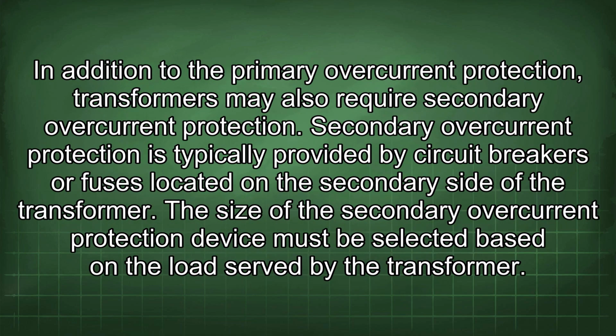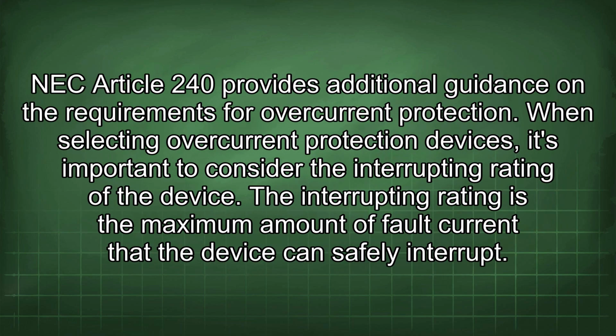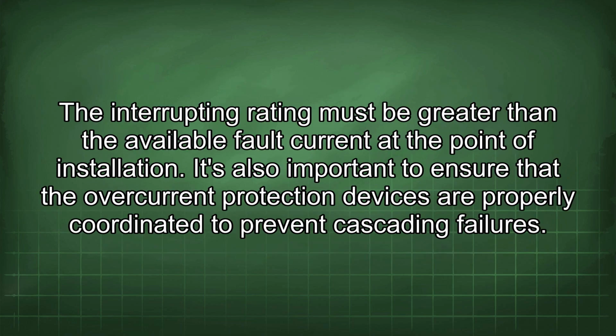In addition to the primary overcurrent protection, transformers may also require secondary overcurrent protection. Secondary overcurrent protection is typically provided by circuit breakers or fuses located on the secondary side of the transformer. The size of the secondary overcurrent protection device must be selected based on the load served by the transformer. NEC Article 240 provides additional guidance on the requirements for overcurrent protection. When selecting overcurrent protection devices, it's important to consider the interrupting rating of the device. The interrupting rating is the maximum amount of fault current that the device can safely interrupt. The interrupting rating must be greater than the available fault current at the point of installation.